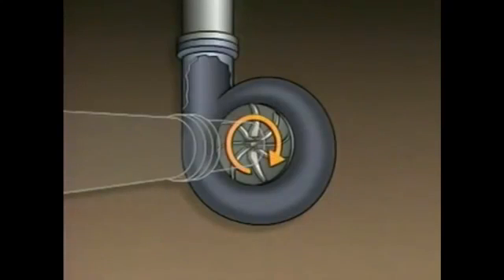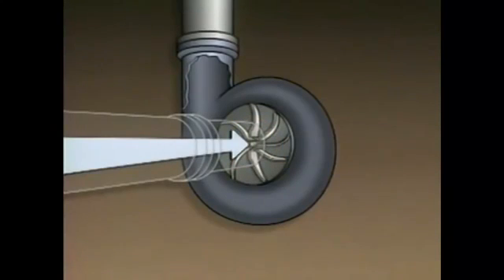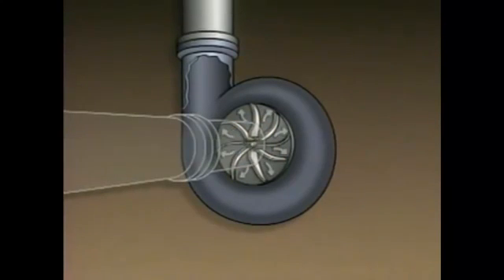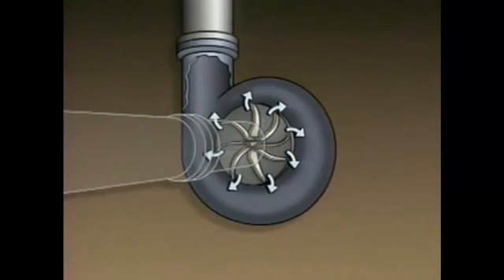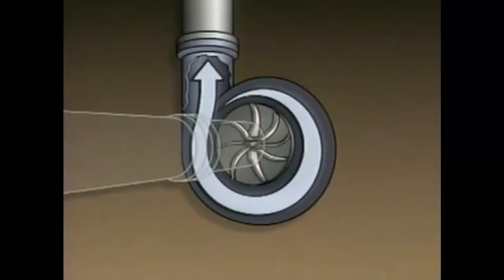As the impeller rotates, gas is drawn in through the suction line to the suction eye. The movement of the gas through the impeller creates a relatively low pressure in the suction eye. This low pressure, in turn, draws more gas into the suction eye. At the discharge vane tips, the gas is traveling at its maximum velocity. From the discharge vane tips, the gas moves into the volute, where it expands and slows down. As the gas slows down, its pressure increases. By the time it reaches the discharge line, it's at its maximum pressure.